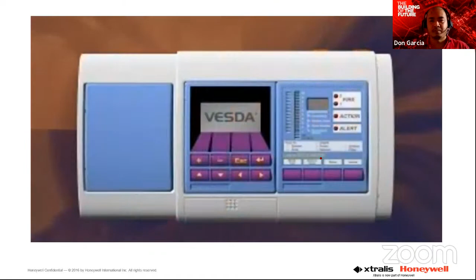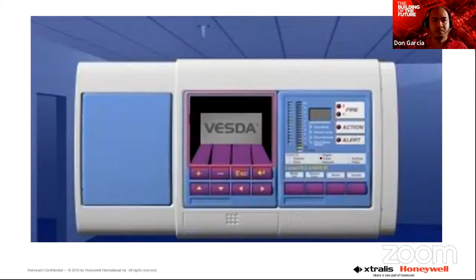This light scatter is instantly detected by a unique configuration of light receiver circuitry, optimized for a wide range of smoke types. The resulting signal is immediately processed and presented via a bar graph display, alarm threshold outputs, and/or graphic display. The VESDA system has 4 smoke alarm threshold levels: Alert, Action, Fire 1, and Fire 2. The sensitivity for each alarm level can be automatically programmed or manually set to a suitable level to fit the condition of the site and to minimize unwanted nuisance alarms.